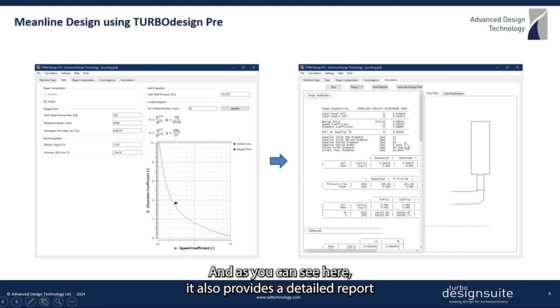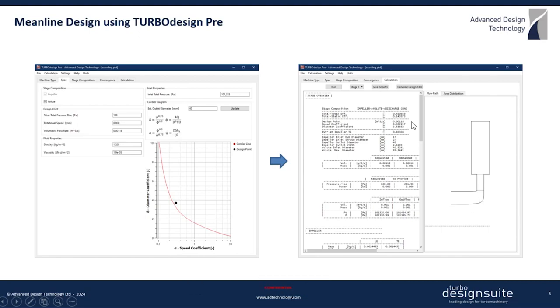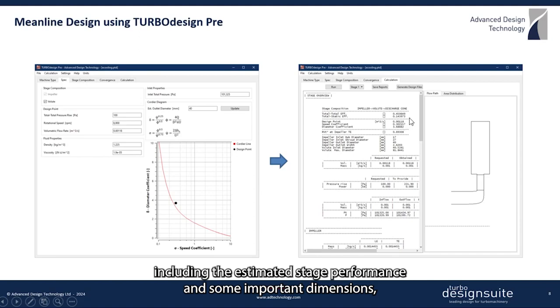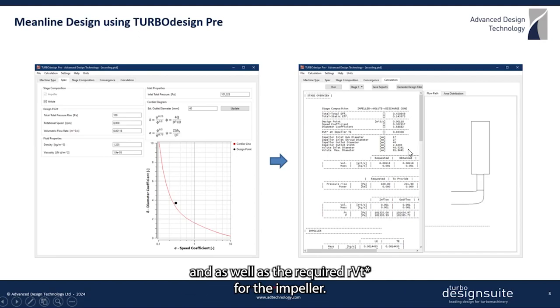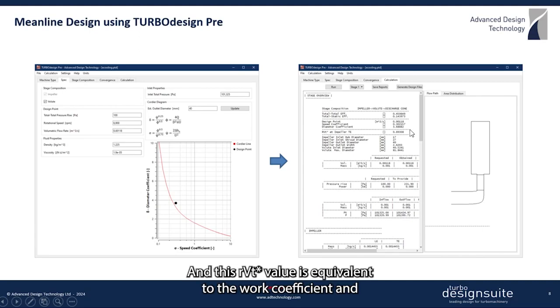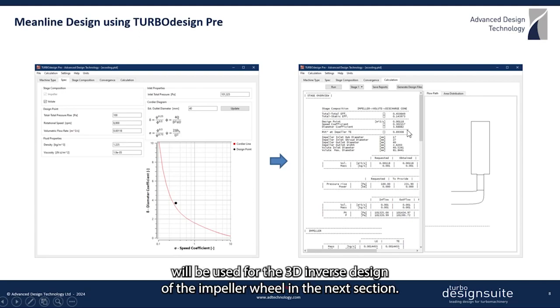It also provides a detailed report including the estimated stage performance, some important dimensions, and the required RVT star for the impeller. This RVT star value is equivalent to the work coefficient and will be used for the 3D inverse design of the impeller wheel in the next section.